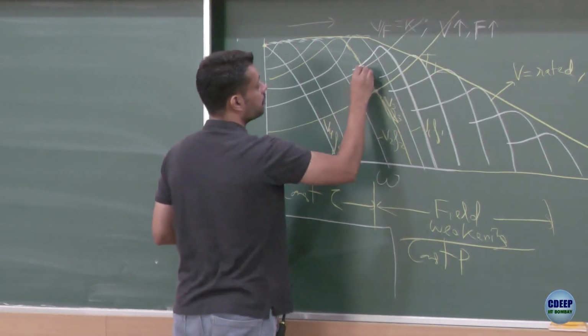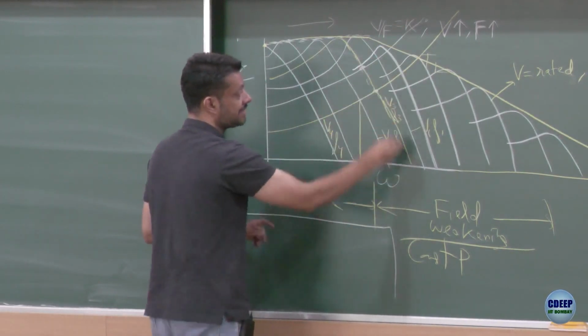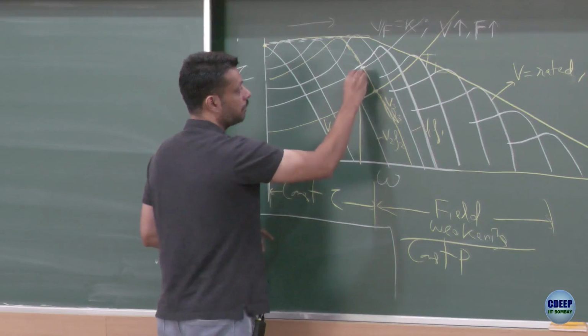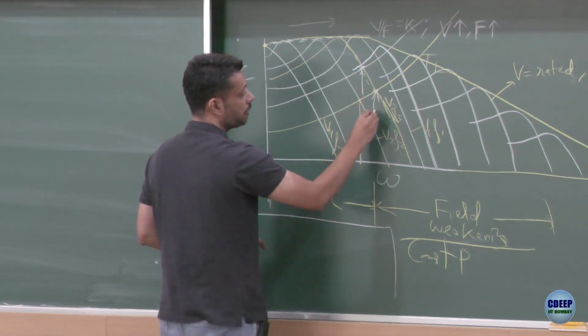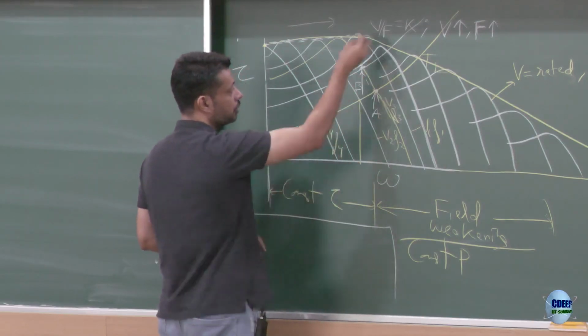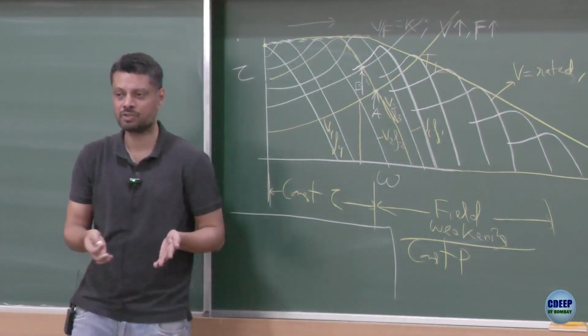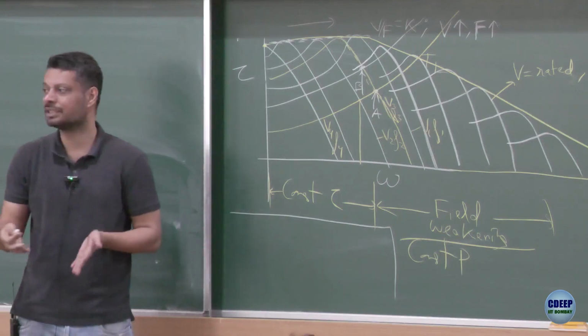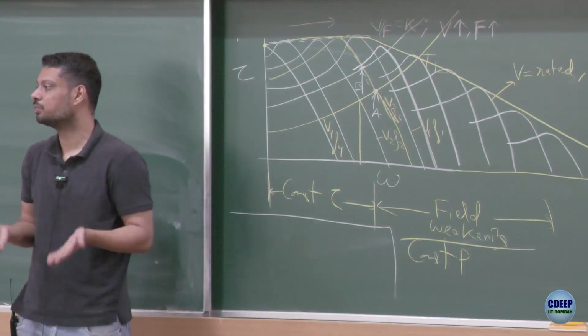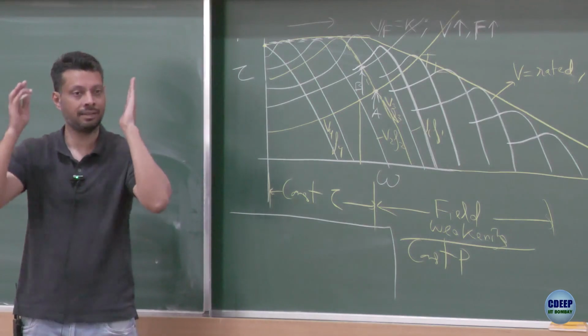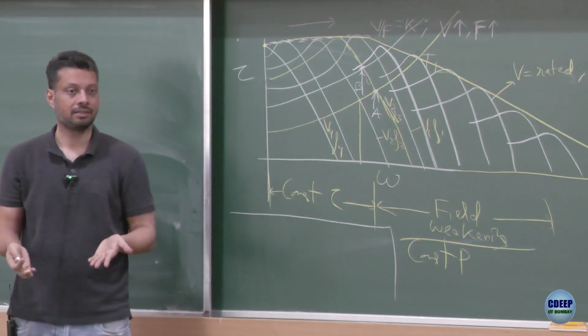your speed will drop. The frequency is the same, but your actual speed will drop, right? Actual speed goes from point A to point B. If you turn on a few more loads, it drops further. So actually your speed was not constant, right? Still changing with the load turning on and off, which is what you would not want, right? You would want your speed to be constant, correct?